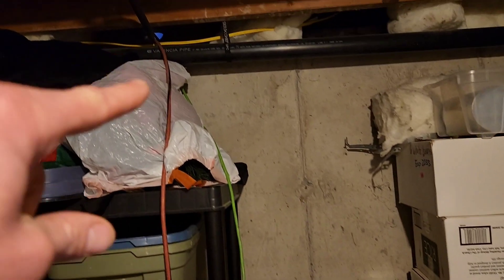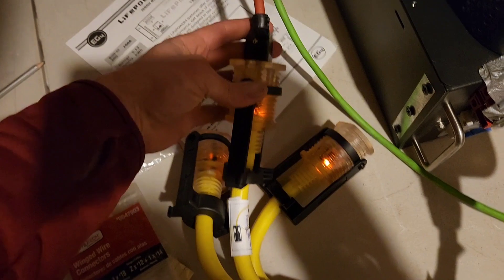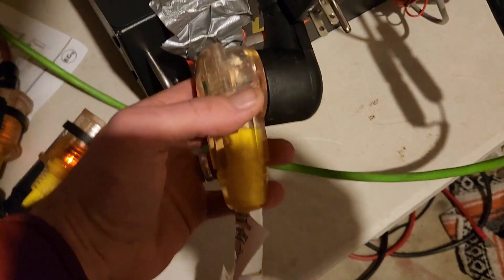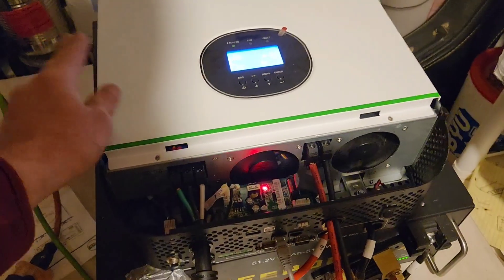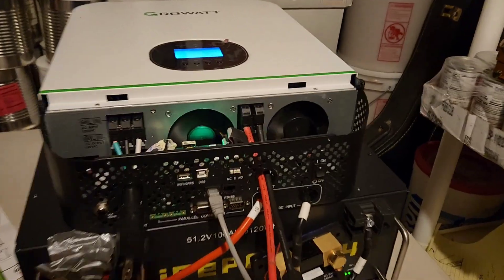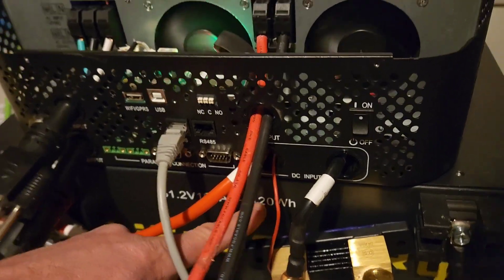I have it plugged in right here, hooking into the charge strip, and then both these go down here. The extension cords come down from here — this is the one that's powering the two fridges. It plugs in here, and then this is my Growatt inverter charge controller. Here are my solar panels going in. I have a lithium iron phosphate battery, 48 volt, 5.12 kilowatt-hours.